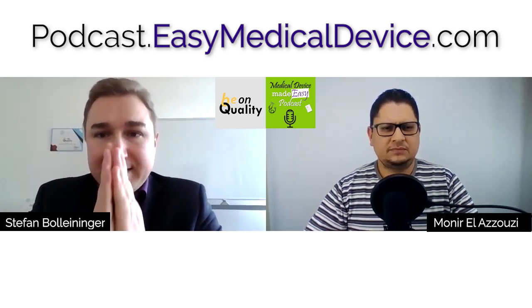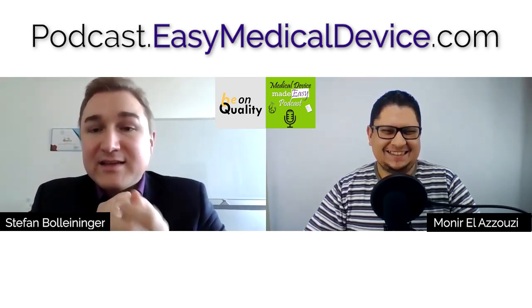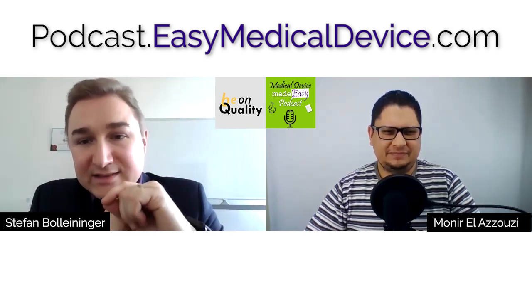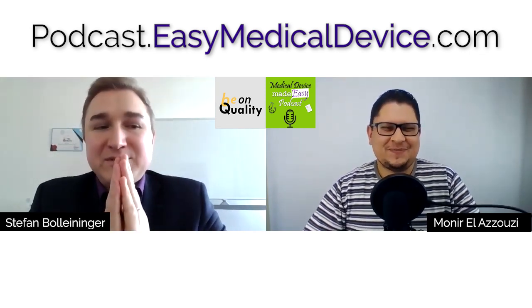So first thing is, how did it happen? Make a good root cause analysis. Or if they found a problem, ask yourself, okay, do I need the fire extinguisher directly? Do I need to make sure that everything's good again? So correction, so immediate correction, is it needed? Yes, no. Decide and don't panic. Don't panic if you have a non-conformity, because, hey, you can clear it. If you find out by the non-conformity that you have products in the market which are not safe, then you need to panic. Everything else, it's a quality management system.